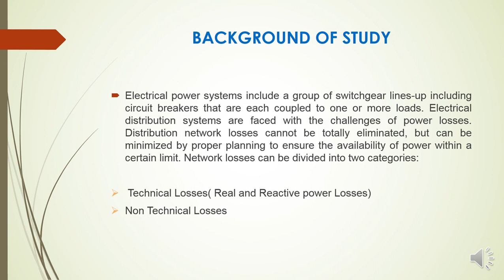These occur due to power losses and voltage drops along the line, and these voltage drops are due to overloading of the substations most times. So every distribution network has several elements in the power system that resist power flow and consume a lot of energy, while granting access to free flow of current through it. That of the Nigerian distribution network has the same problem too. The problems of losses and voltage drop in these distribution feeders are dependent on one another, but vary with the pattern of loading on the feeders.